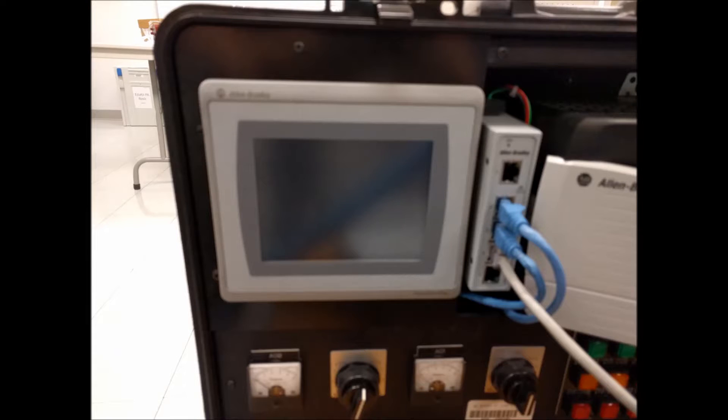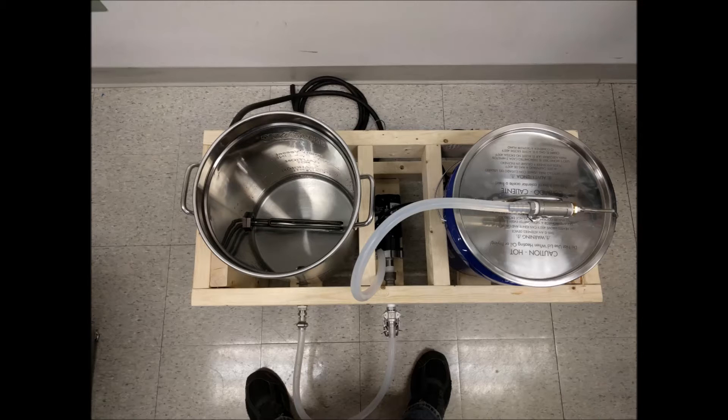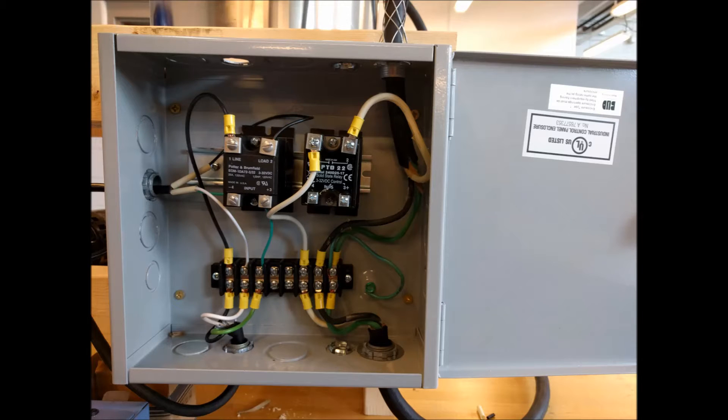The system uses a PLC equipped with a human machine interface touchscreen for control. To heat the water, a heating element was installed in a stainless steel kettle. The heating element is controlled with a solid-state relay that switches 240 volts on and off as directed by the PLC.